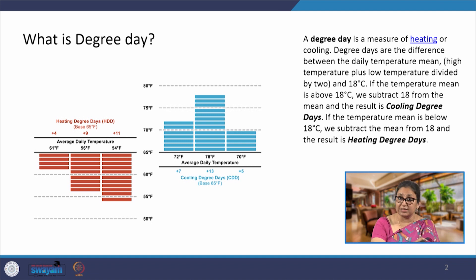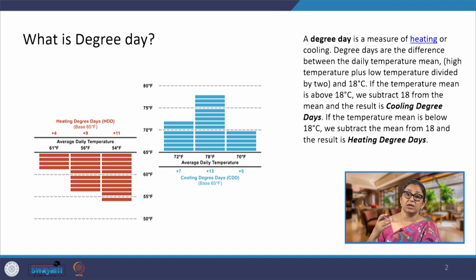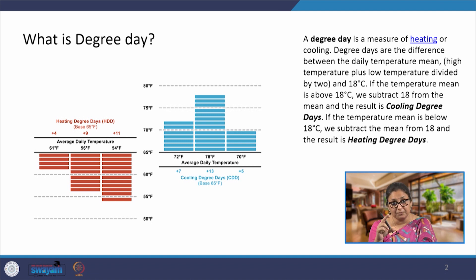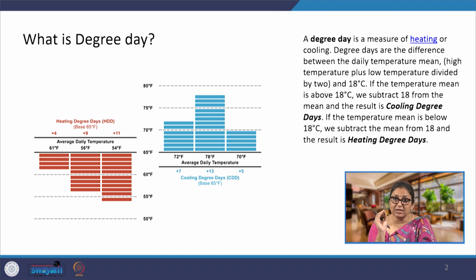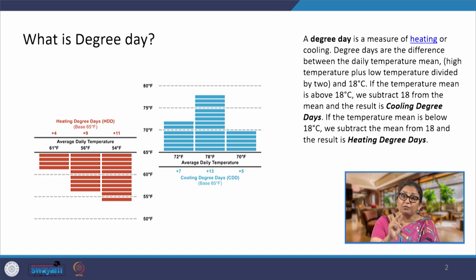If we look at the United States of America, the standard temperature used to calculate degree days is 65°F. In India, we have set it at 18°C — almost similar, but we would consider 18°C as the standard temperature. To calculate cooling degree days, we take the average of the daily minimum and maximum temperature, subtract the standard temperature from it, and the difference is the number of cooling degree days. For every degree rise above the standard temperature for one day, it is equivalent to one degree day.